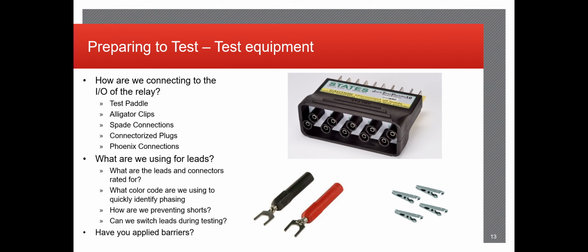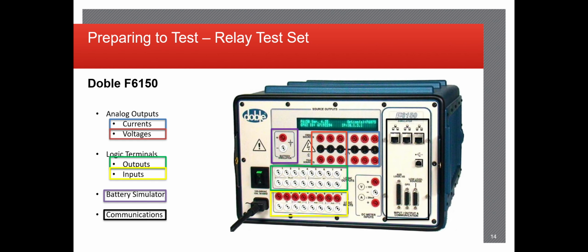Barriers are also extremely useful for designating the relay cabinet that you're going to be working in. If you show up on site and you've found the panel that holds the relay that you're going to be testing, you want to make sure that you barricade as much of the surrounding equipment as possible without operating anything for sure. This is just to make sure that if you say you go out to lunch, come back, and you don't even think about it, you just plug in your test paddle, some random relay, and start pushing currents and voltages, that might cause a trip, which could be bad.